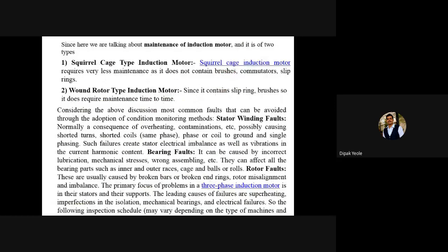Now we are interested in the two types of induction motors: squirrel cage and wound type. The squirrel cage induction motor requires very less maintenance as it does not contain brushes, commutators and slip rings, so that is an advantageous motor. But whenever we are using a wound type motor, it contains slip rings and brushes, so it does require maintenance from time to time. This is a very important difference in maintenance between squirrel cage and wound type motors.